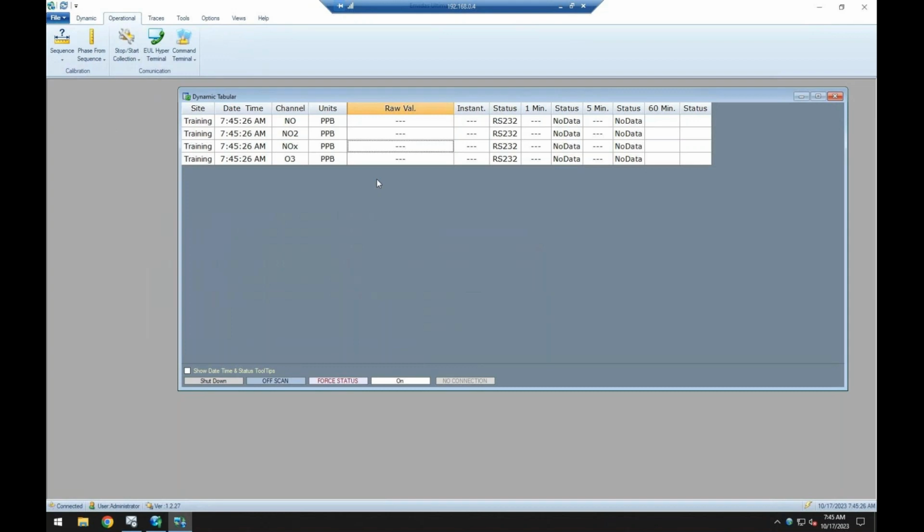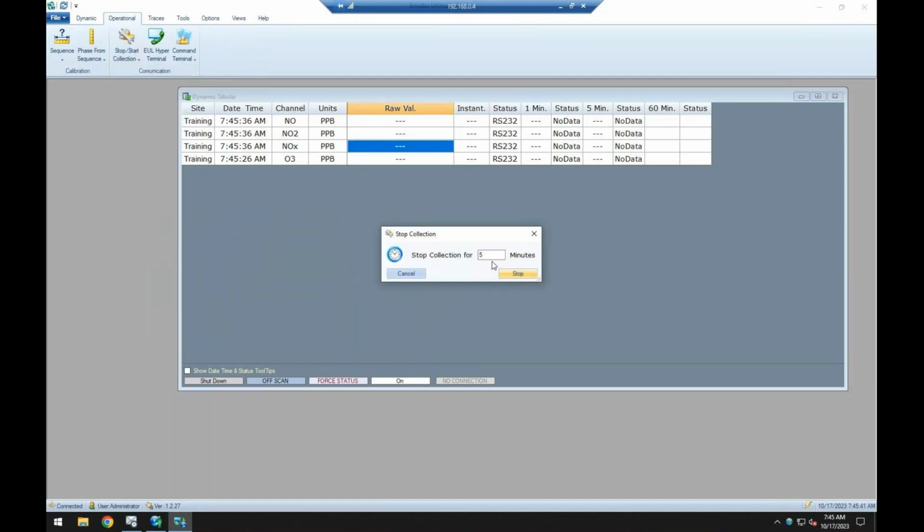There are other ways of doing that. You could stop the Ultimate service and then connect to it with iPort, but if you do it that way, data collection for all instruments would stop during that period. Whereas with this, if you just say stop port 2, only it would stop the communication and everything else would continue logging data.